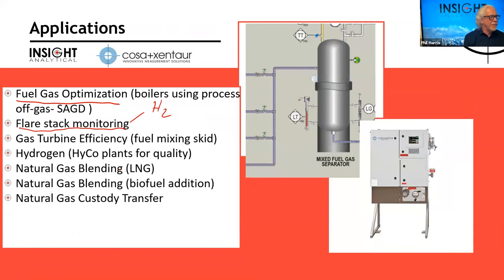If you have really big variations in your hydrogen content, you can be 60% hydrogen one day, 10% the next day, we put in an additional sensor, either a thermal conductivity sensor or a microgas chromatograph, just to try to quantify that hydrogen better. So if your hydrogen is a relatively minor component of the gas composition, you can tune that out with calibration. But if it's really varying a lot, if it's the primary fuel, you may have to add another sensor in to better quantify that hydrogen number.